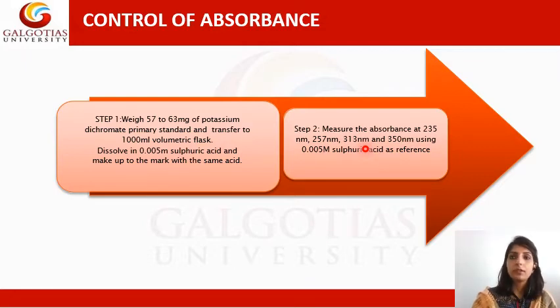For measuring the absorbance, we require particular wavelengths. The wavelengths are specific. So we will measure the absorbance of this solution at 235 nanometer, 257 nanometer, 313 nanometer and 350 nanometer, using 0.005 molar sulfuric acid as reference. The reference solution that you will put in your reference cuvette is 0.005 molar sulfuric acid, and in the sample cell you will place the potassium dichromate solution that you have prepared, and you will measure the absorbance at 235, 257, 313 and 350 nanometer.